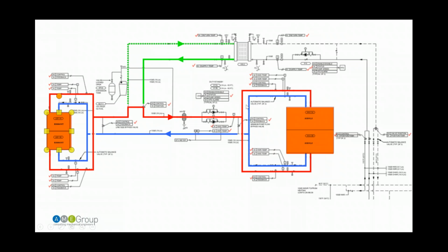And so we're going to be going through that supply, recovering as much heat as we can through the exhaust, and then topping up any heat that we need through the heat exchanger and then into our supply air handler. And so through this, we were able to really increase the effectiveness of our system and reduce the pressure drops through our supply air handler as well, which has added to the efficiencies that we've gotten in the building.